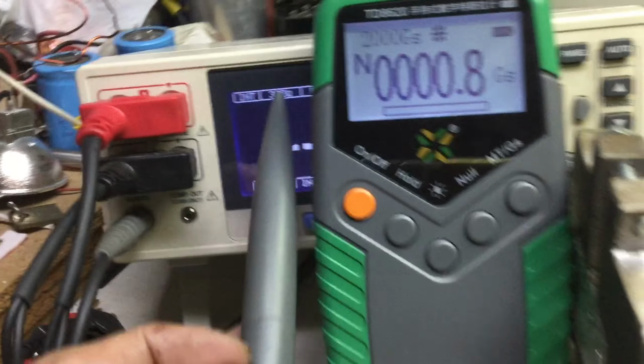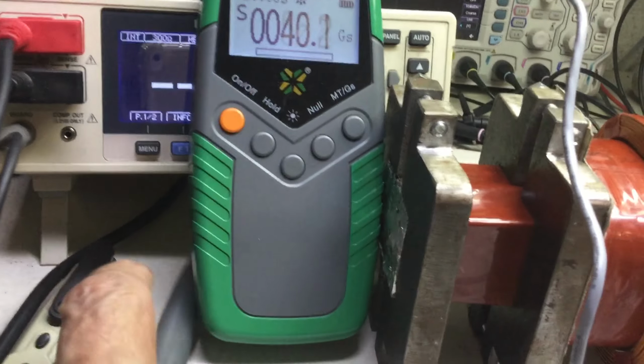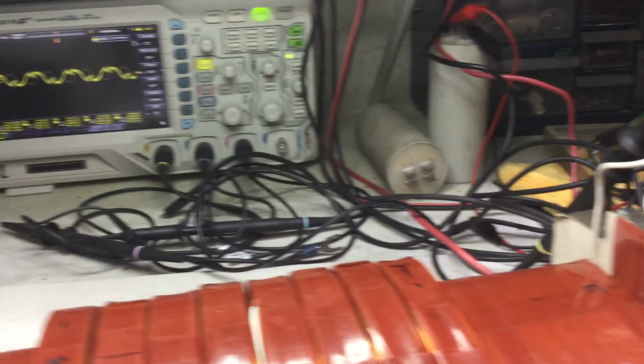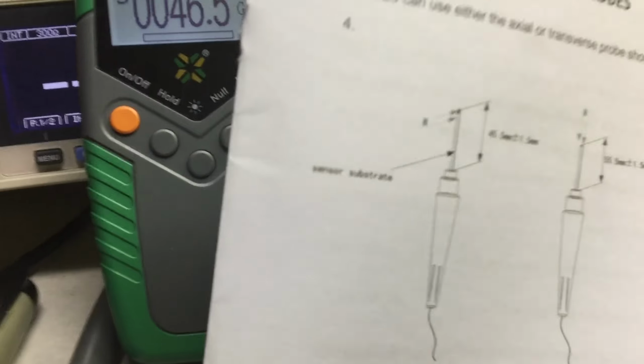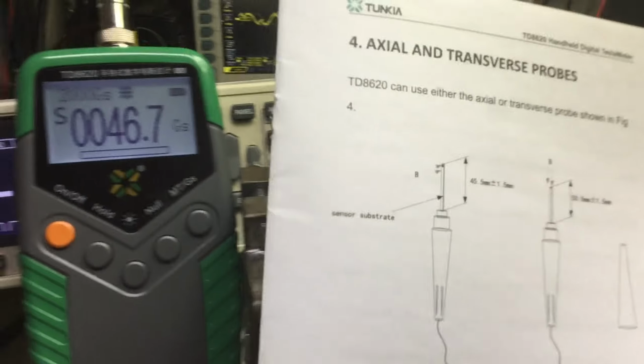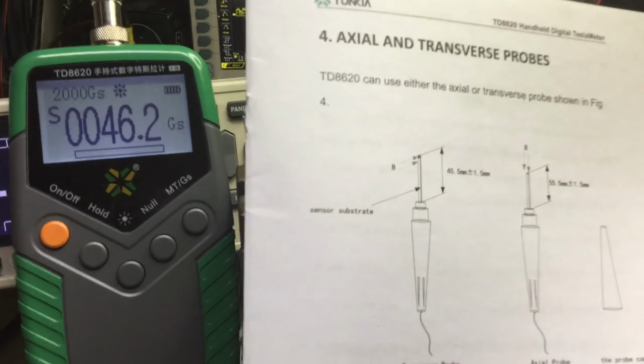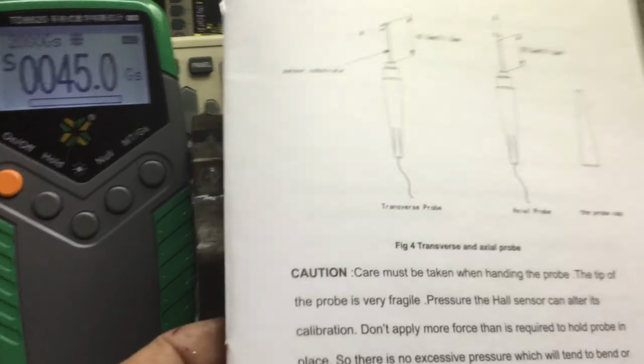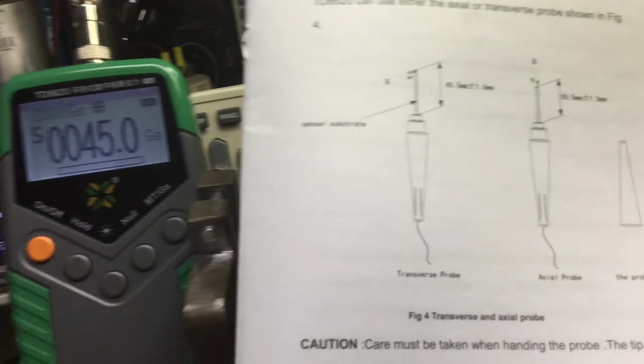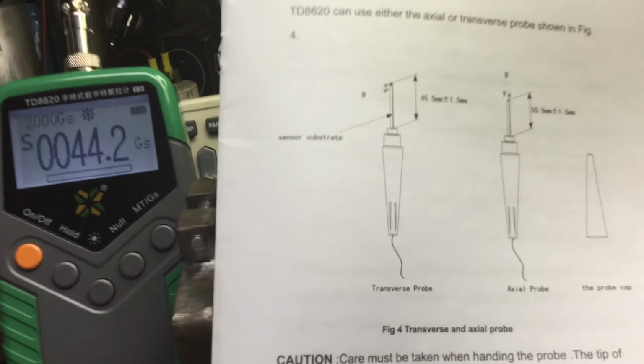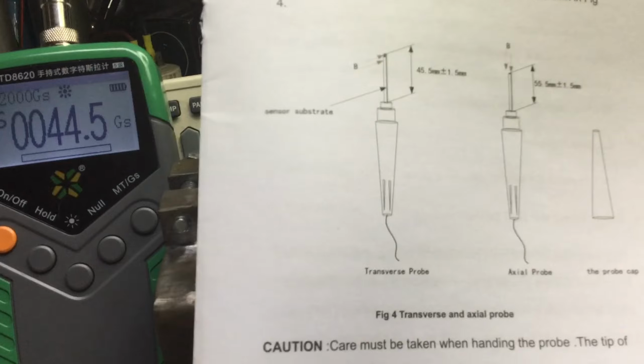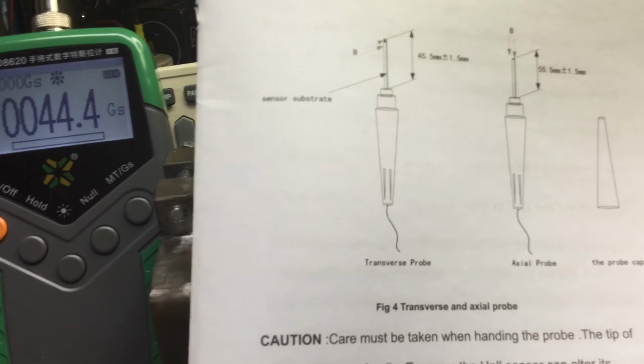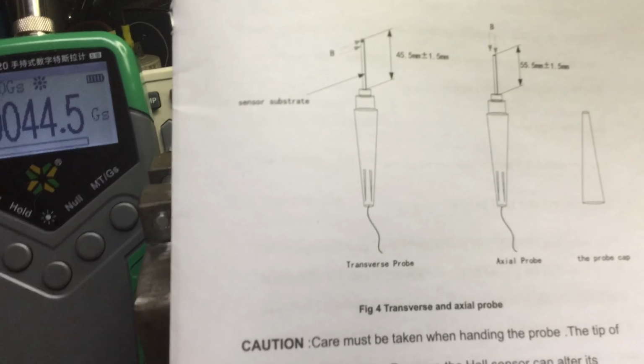One thing about this meter, and this is the reason the reading came out wrong on the testing done before: this probe can be replaced. It doesn't come with two probes, just one, and it's the transverse probe. The other one is the axial probe. It doesn't come with it; you have to order it separately.